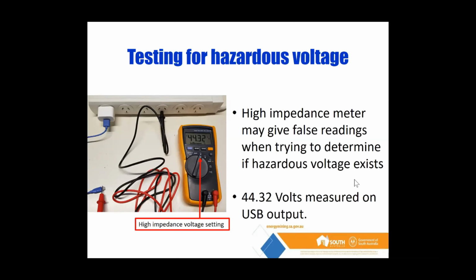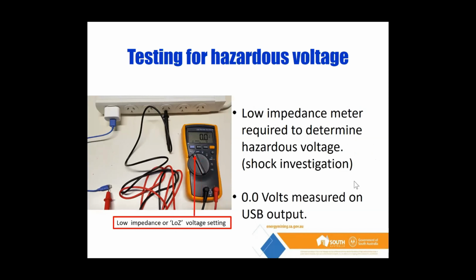If you notice, the meter in this situation is actually on volts AC. So we should be getting the voltage that we're trying to measure for, right? Then if we pulled out our wiggy, we'd find that we would be getting 0 volts. That's because the wiggy is actually putting a bit of load on the circuit, and it's getting rid of what we call that ghost voltage, as it were. So if we flick the meter to the low impedance setting, this meter actually has that availability, it then gives us a different story. We're measuring for the exact same thing, volts, however with a different type of meter now, and it's telling us that we've got 0 volts. And this is really important when we're performing shock investigations where someone's been hurt or injured, because we can get put off the scent if we're utilising the wrong meter.